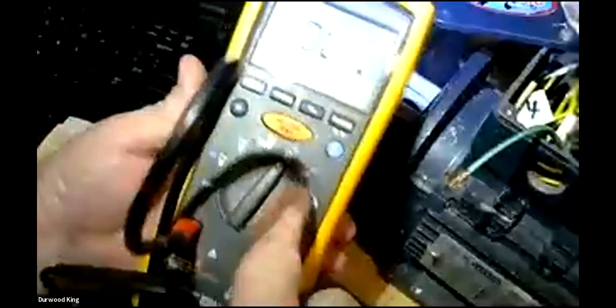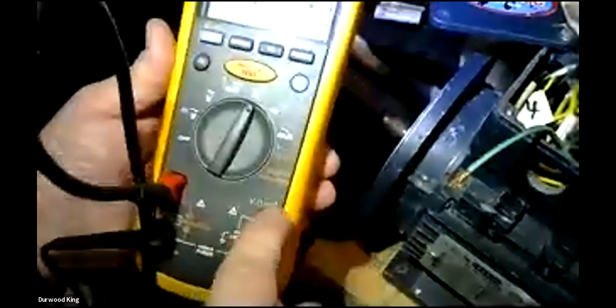So to check continuity through the motor, going through the windings, you can actually use that basic meter there to do it. You don't have to use this. If you use this, you got to switch over to the other probes and then change the setting to ohms, okay? So if you were going to do it on this one, you put it on ohms, and you got to put a probe in here and put one in there, okay? You switch over to here like that.